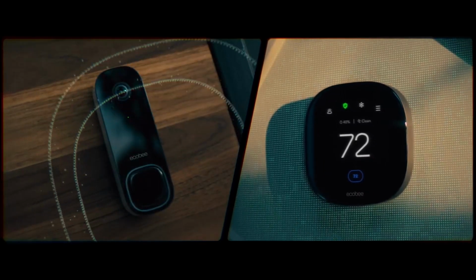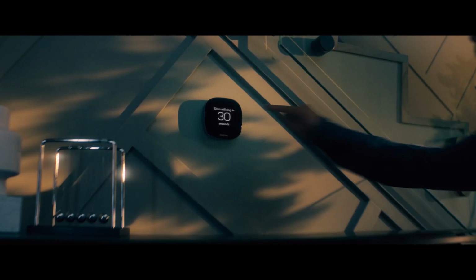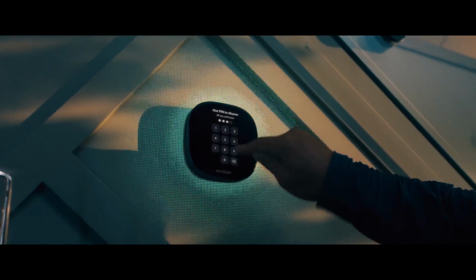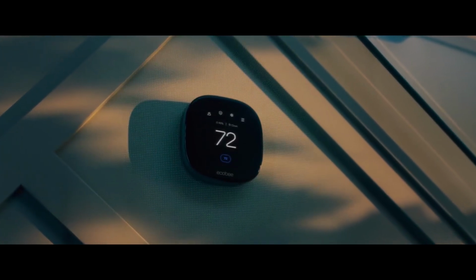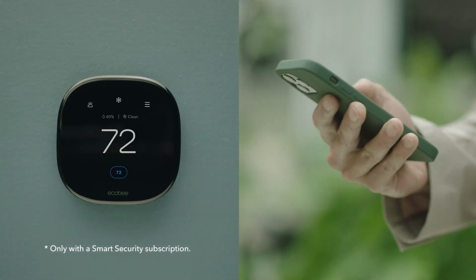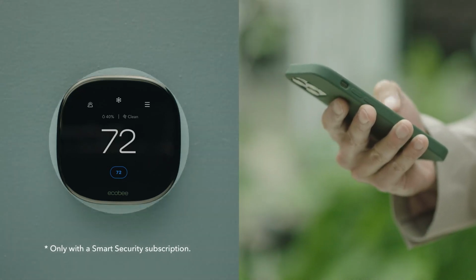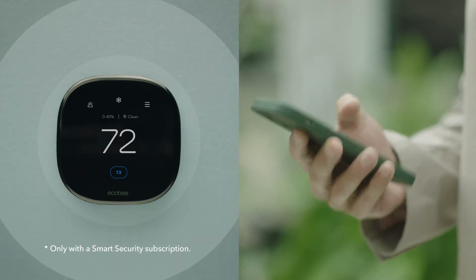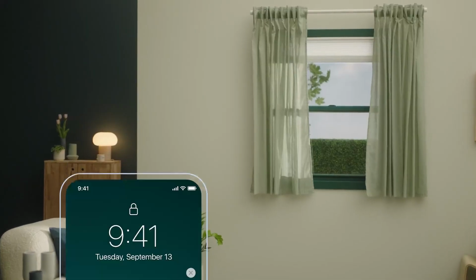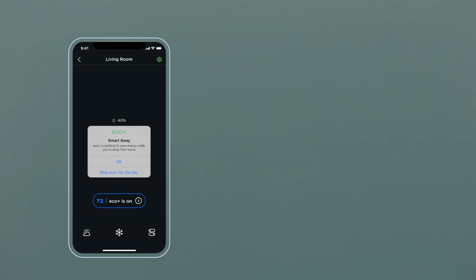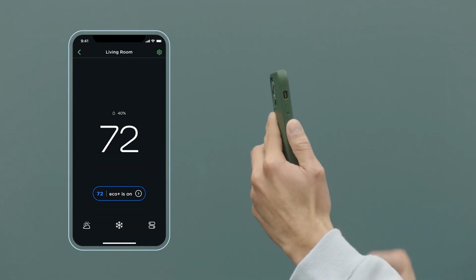Next, check the thermostat's calibration. A slight shift in calibration can lead to errors in the temperature readings. Compare the thermostat's displayed temperature with a reliable thermometer placed nearby. If discrepancies are found, follow the manufacturer's instructions to recalibrate the thermostat. Some models have automatic calibration features, but for others, manual adjustment might be necessary.